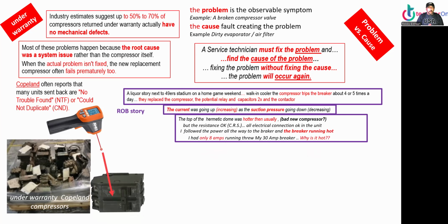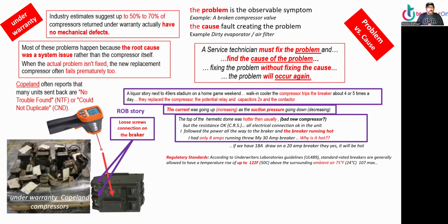There we go. I only had 8 amps running through my 30 amp breaker. Why is that hot? Loose screw connection on the breaker. If we have an 18 amp draw on a 20 amp breaker, then yes, it's supposed to be hot. According to the regular standards, a breaker should generally be at maximum 122 degrees, if ambient air is 75. That sounds right. My breaker was running about 150, 160.